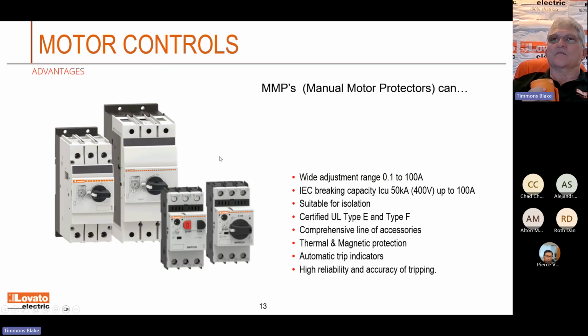And your motor protectors, we do have quite a wide adjustment range on them. Breaking capacity is 50 kA, UL type E and F. I don't know if you guys get into that. If you don't, usually these 508 shops do. Type E means you can kind of use it for a service entrance.